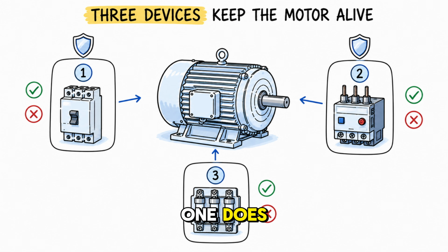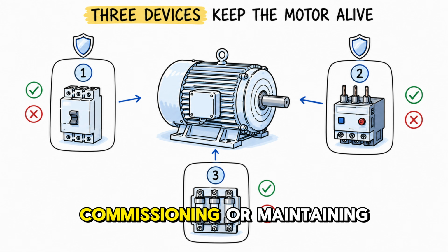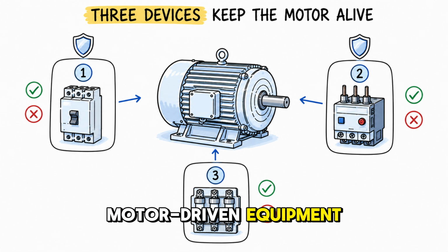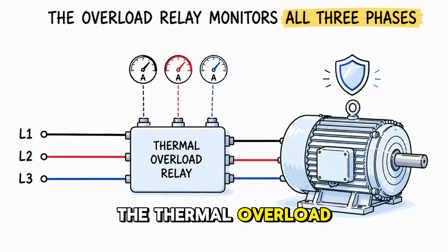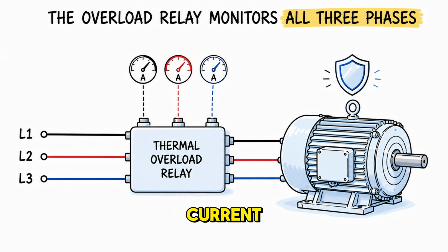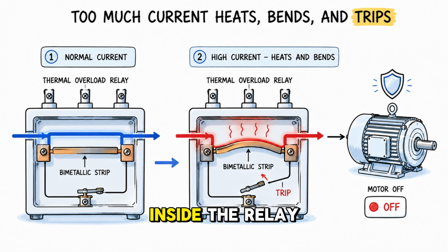Understanding what each one does and what each one does not do is essential for any engineer commissioning or maintaining motor-driven equipment. The first is the thermal overload relay. It monitors the current drawn by the motor on all 3 phases simultaneously. Inside the relay, a bimetallic strip heats up in direct proportion to the current passing through it. When the current exceeds the set threshold for long enough, the bimetallic strip bends far enough to trip a contact and shut down the motor.